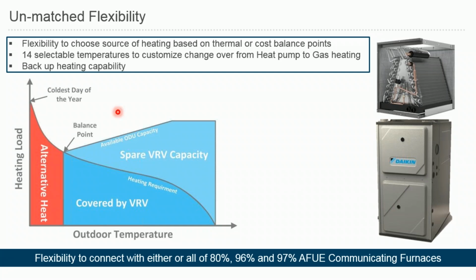Basically, what the system does is it looks at the outdoor unit thermistor temperature, whatever that thermistor detects from outside air, and it makes this switch happen between gas furnace and heat pump heating. And you can change this balance temperature based on maybe the climate requirements, or maybe you're changing utility rates. Maybe gas is cheaper in your region and you want to use gas heat for heating most of the time, or maybe you still want to leverage heat pump heating down to a certain temperature, maybe like the 20s, 30s, and below such temperature, you want to start your gas furnace heat and provide your heating from there.